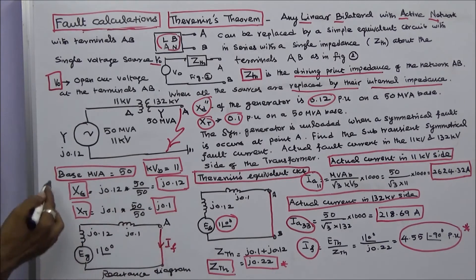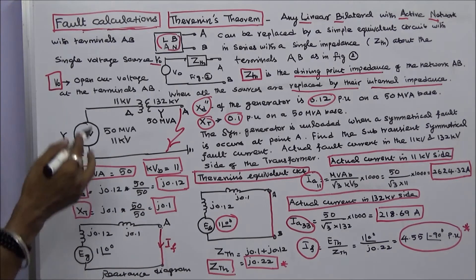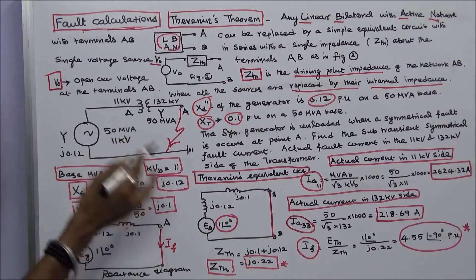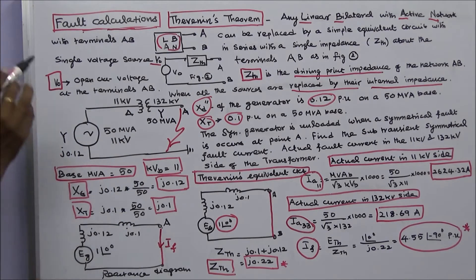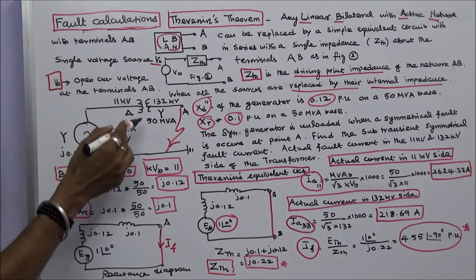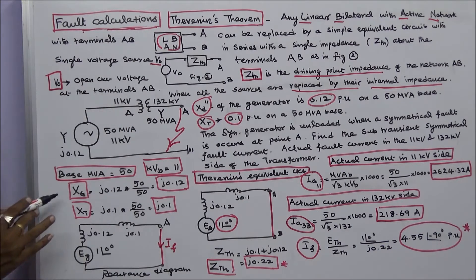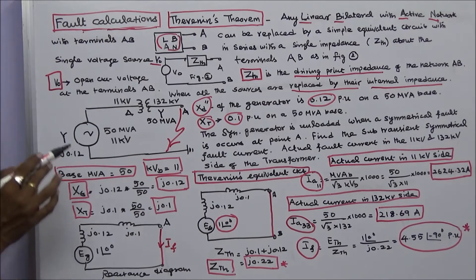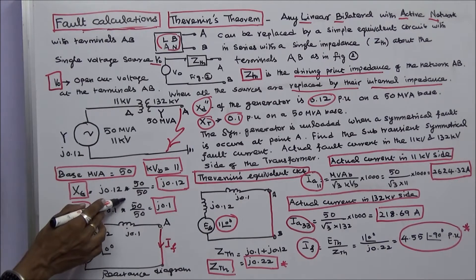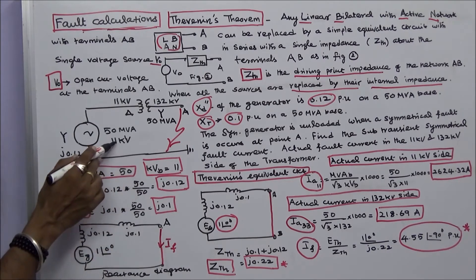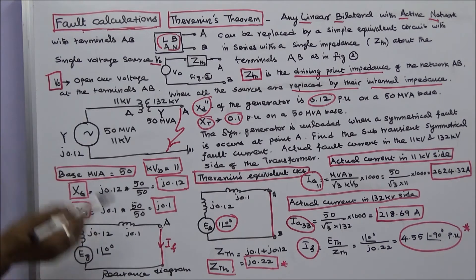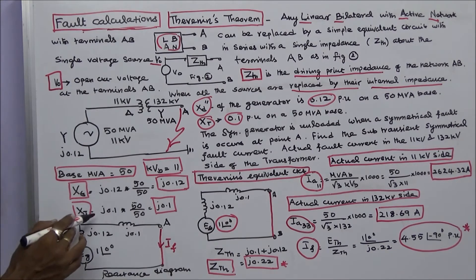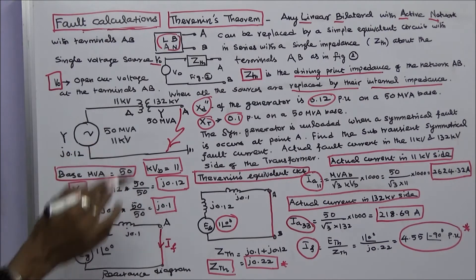First step, we choose base MVA. Base MVA is equal to 50. Base kV is equal to 11. Next, I calculate the per unit reactance of the generator and the transformer. Per unit reactance of the generator is equal to actual reactance j0.12 multiplied by actual MVA over base MVA, which is 50 over 50. Therefore reactance of the generator is j0.12. Similarly, reactance of the transformer is j0.1 into 50 by 50, that is equal to j0.1.